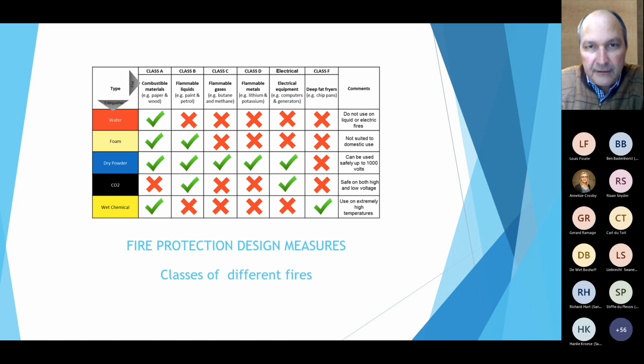Unfortunately, I have to leave this meeting, and I really would like to stay on. But in terms of that class A and that table of combustible materials, for instance paper and wood, we have also noted in the frequency of occurrences of gas explosions that paper and wood in the wood industry have a significantly higher frequency than in grain storage, especially grain and oilseed storage. So I would love to see a class A minus there, because our risk in the storage sector is much less than where you need to process maize and sunflower seed into a product. I'm of the opinion that we are at a lower risk in terms of that.